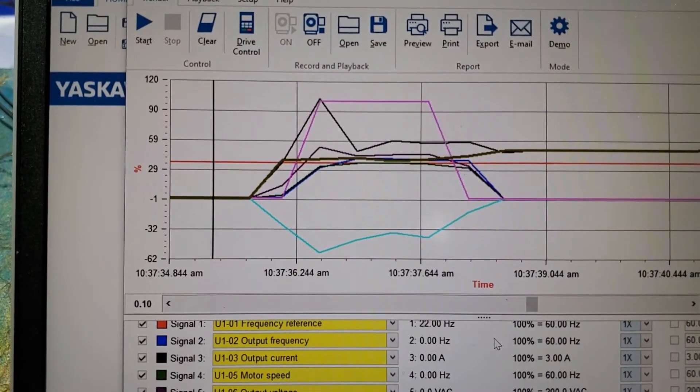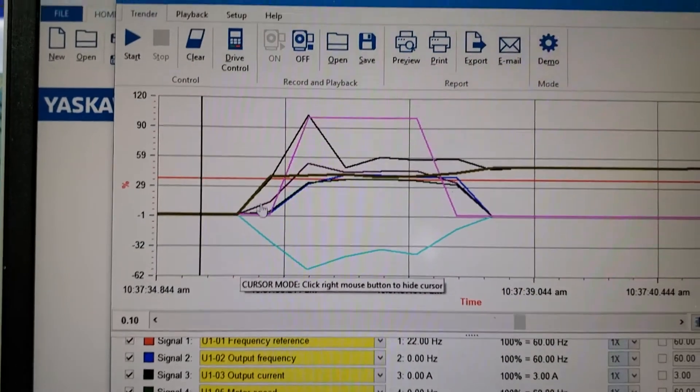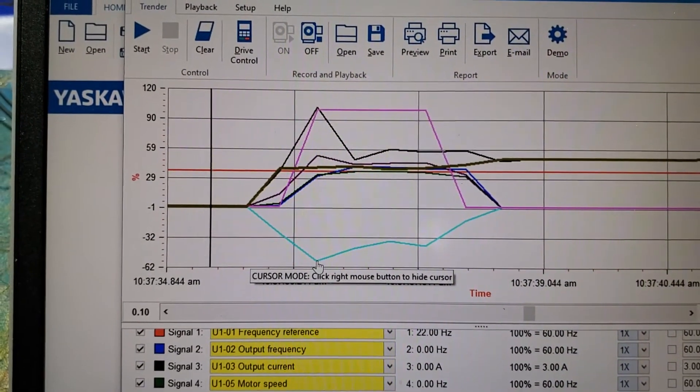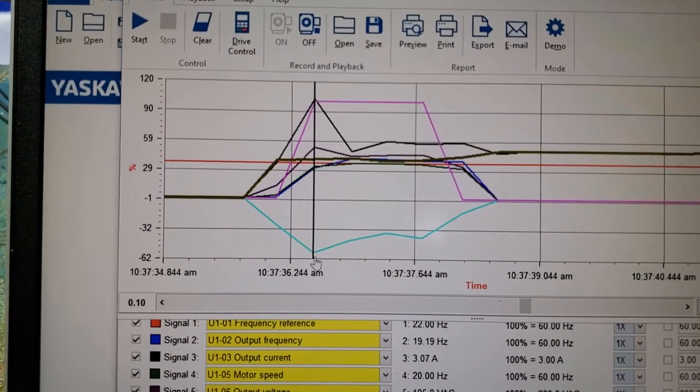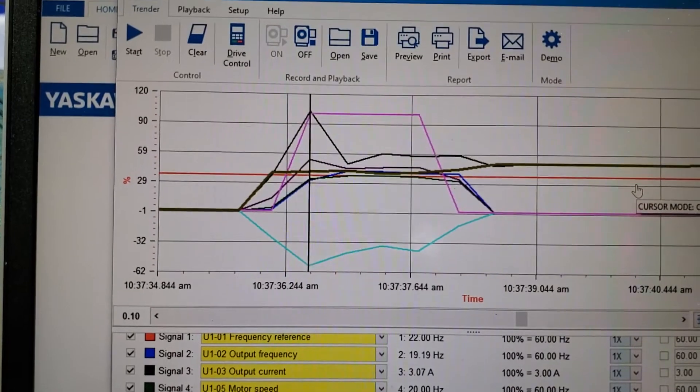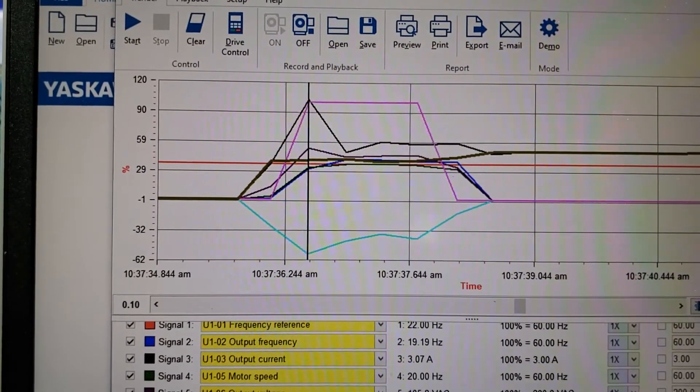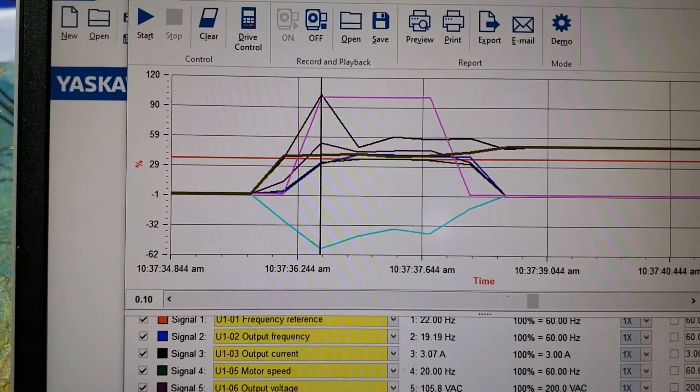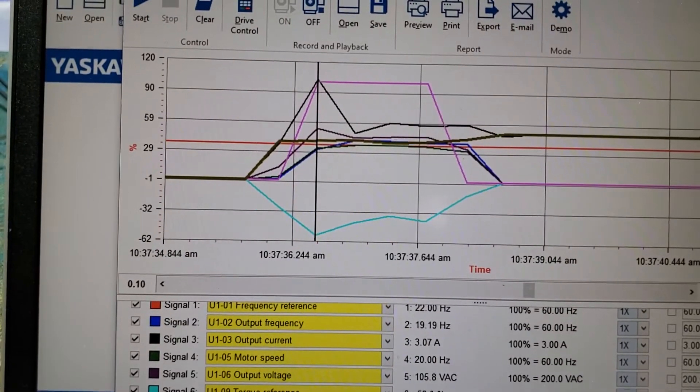So for torque, for instance, if I go to the highest point in torque, it shows me torque was at negative 56%. It's negative because it was in reverse.